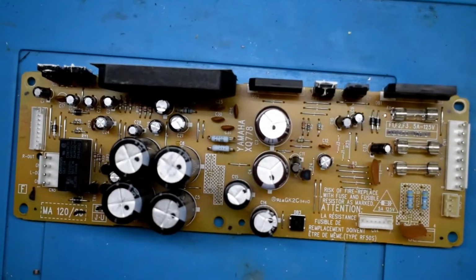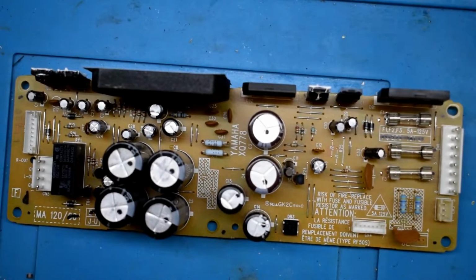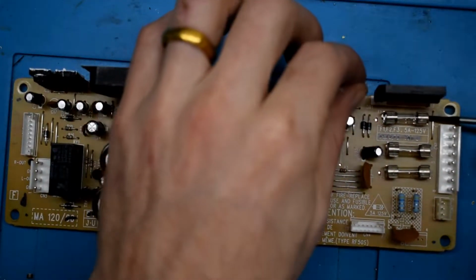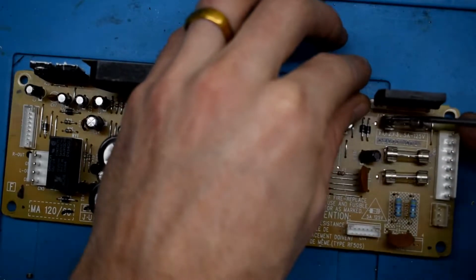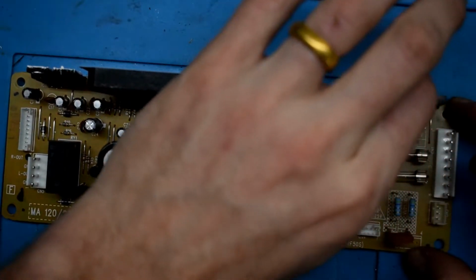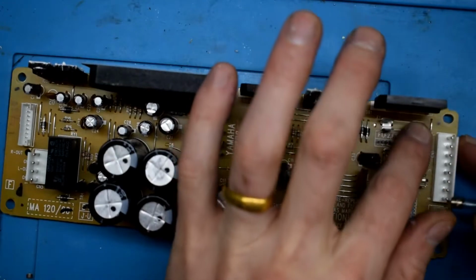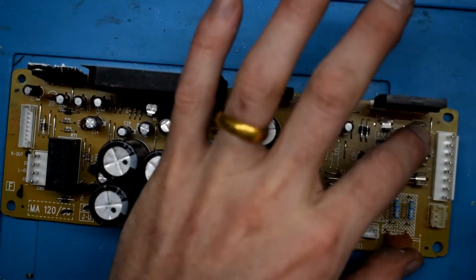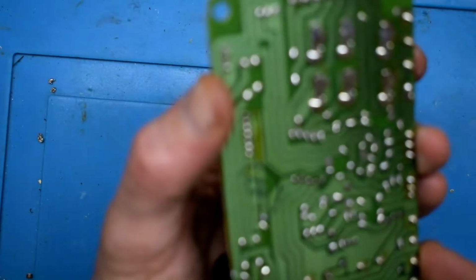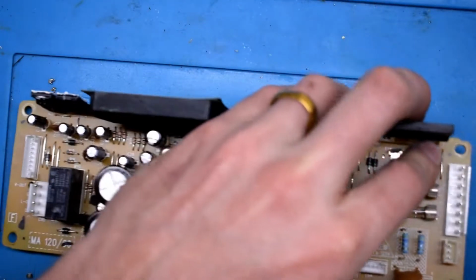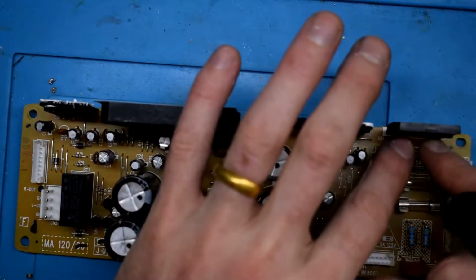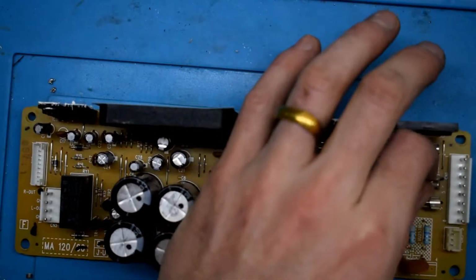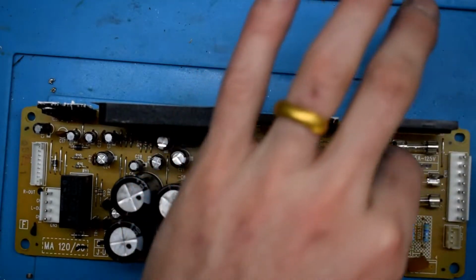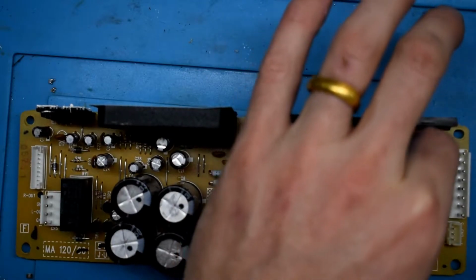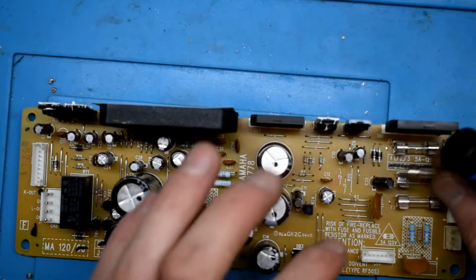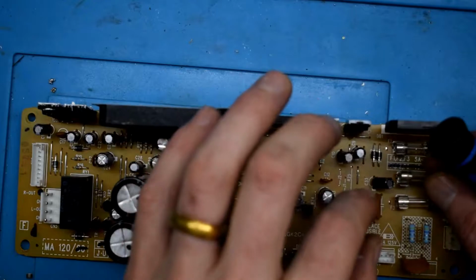Could be a loose connection because it's intermittent, so it could be these kind of fuse holders—you see they're kind of wiggly. So disconnect these fuses, just wiggle them around, and you can pinch the holders together.